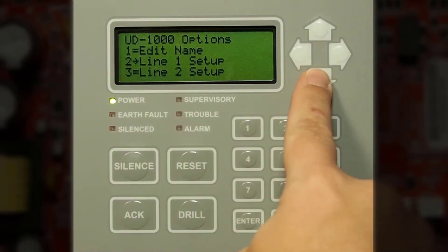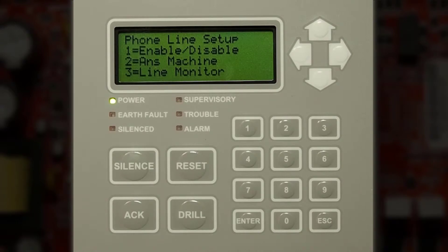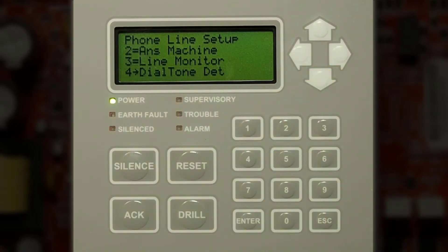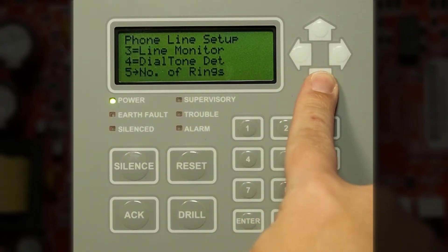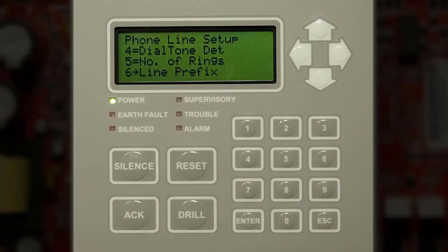You can adjust line one or line two setup. In order to enter the setup you'll need to press enter. You can enable or disable phone line one or phone line two, enable answer machine bypass, enable or disable line monitoring which is checking for the voltage in the telephone line, enable or disable dial tone detection, choose the number of rings in which the panel will pick up if dialing into the control panel, or the line prefix — if you have to enter a number to dial out you would enter that here, such as a nine to dial out.